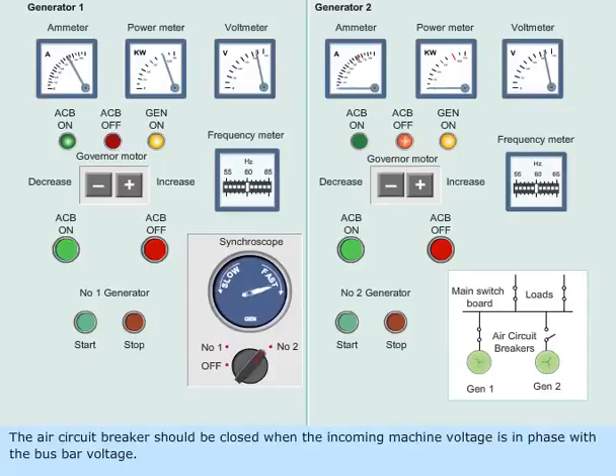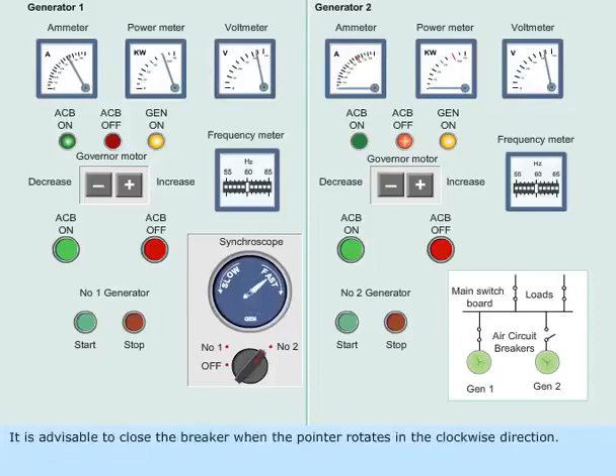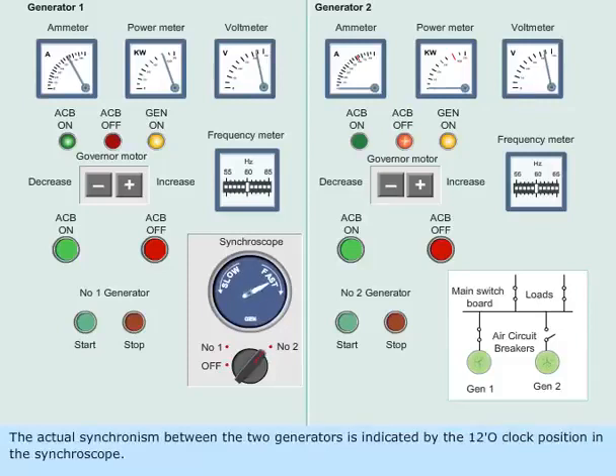The air circuit breaker should be closed when the incoming machine voltage is in phase with the bus bar voltage. It is advisable to close the breaker when the pointer rotates in clockwise direction. The actual synchronism between the two generators is indicated by the 12 o'clock position in the synchroscope.